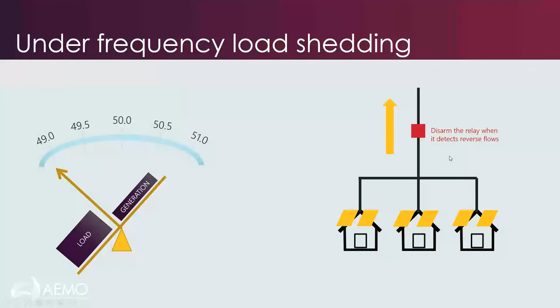It should be operating on a circuit to disconnect a net load, but as we have a reduction in that load due to it being supplied locally, the UFLS becomes less effective. And when we get even more PV on the circuit and it starts going into reverse flows, it will actually exacerbate a frequency decline. A further complication too is that the PV itself will disconnect when there's a frequency disturbance, and that can also exacerbate the frequency decline.